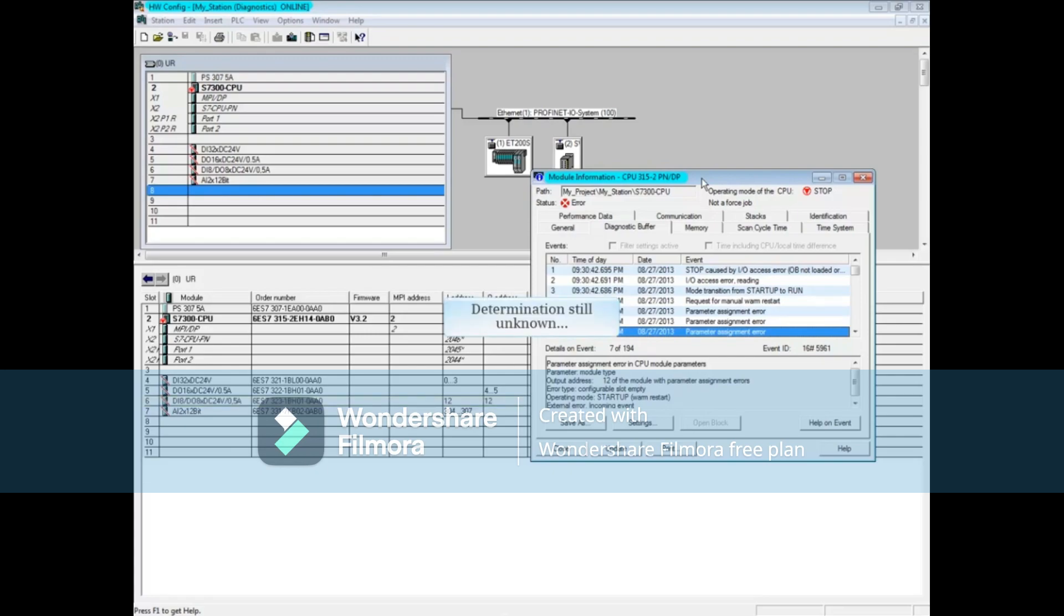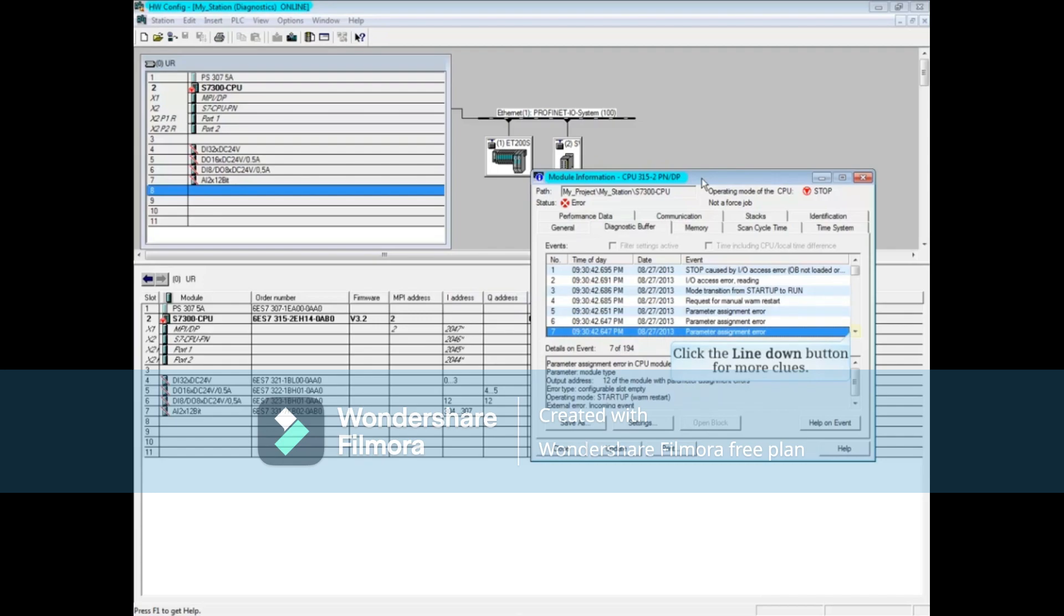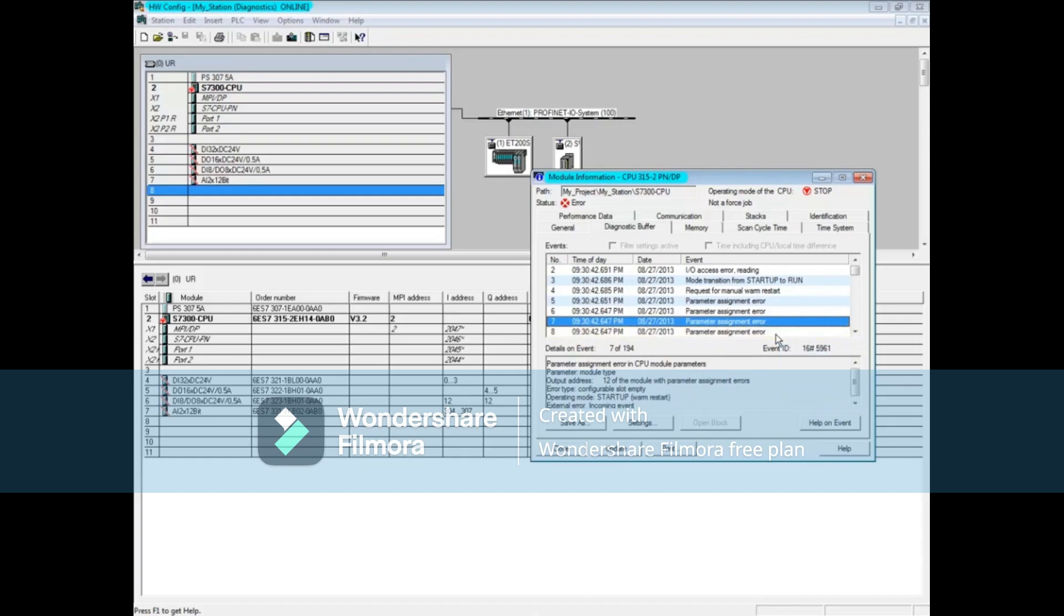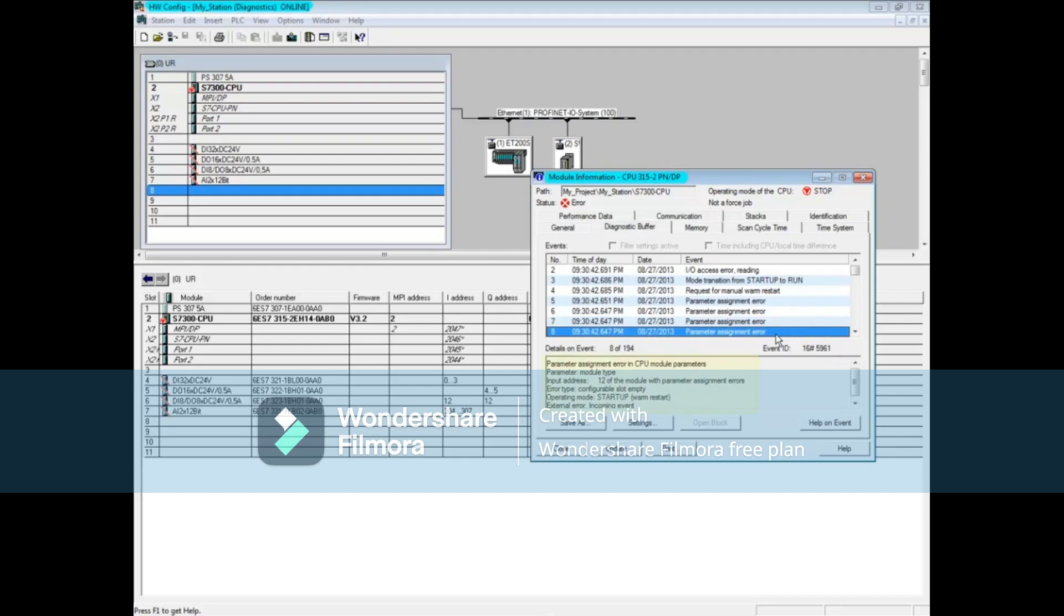We still cannot determine what has happened. Let's look down the message list for more messages. Click on message 8, also a parameter assignment error. Message 8 says the input address 12 could not be read. This address also belongs to slot 6, the digital in digital output module.